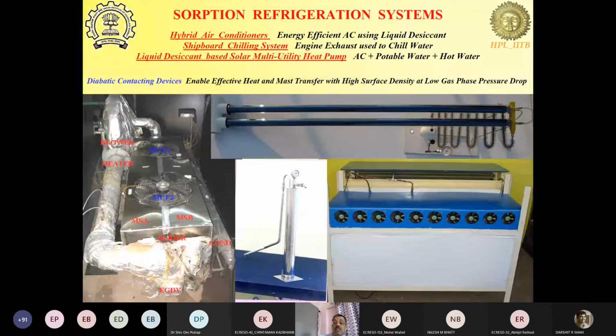So here is a solar refrigerator cum water heater module, where the adsorption modules are covered with an evacuated glass tube, and the modules get heated up to 180 to 200 degrees centigrade during the day when the sun is shining. Then the ammonia is regenerated and condensed using the wire fin technology here. We collect the condensed ammonia, which evaporates during the evening or night when the sun goes down and the modules cool down, or we circulate tap water in this and heat up the water by recovering heat from this. So this unit not only produces a cooling effect, but also produces hot water from the same system. The refrigerator cum water heater is based on this technology.